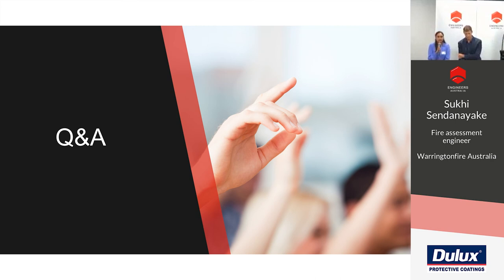So that's the minimum thickness that needs to be applied. And in terms of precision, it's coming from the regression equation. When we input the results of the time taken for each of the section factors to achieve limiting temperatures, we can use that precision based on the raw test data. So if, for example, 3.74 to 3 decimal points is the minimum, then that can be rounded off. Within the points, we can also interpolate between them. So if a different section factor or other thicknesses are needed, then between minimums and maximums, that can be interpolated as well.